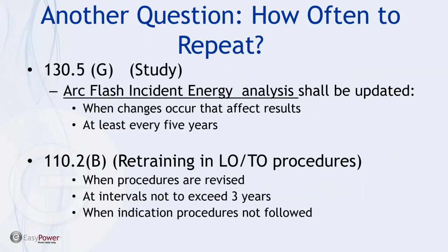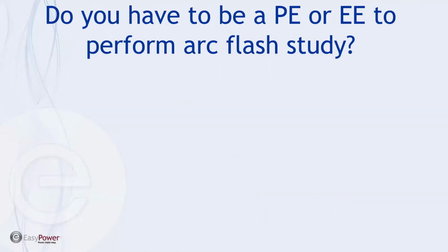Here's another question. How often do you repeat the study? Well, I want to point out that NFPA 70E suggests that any change that affects the results of the study requires you to update the study, or at a minimum every 5 years. Comparing that to what's required for retraining, especially in lockout tagout, if the procedure is revised, people need to be retrained, and at least every 3 years. The point being, it's recognized that better training, better procedures, documentation, and system controls have more of an effect in preventing accidents as opposed to the PPE being worn, because that just reduces the amount of damage one receives during an arc flash event.